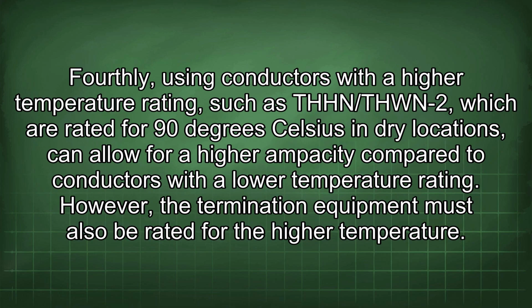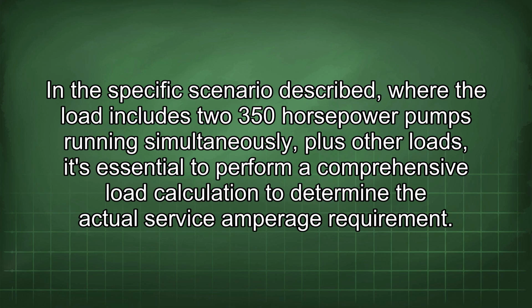Fourthly, using conductors with a higher temperature rating, such as THHN/THWN-2, which are rated for 90 degrees Celsius in dry locations, can allow for a higher ampacity compared to conductors with a lower temperature rating. However, the termination equipment must also be rated for the higher temperature. In the specific scenario described, where the load includes 2 350 horsepower pumps running simultaneously plus other loads, it's essential to perform a comprehensive load calculation to determine the actual service amperage requirement.